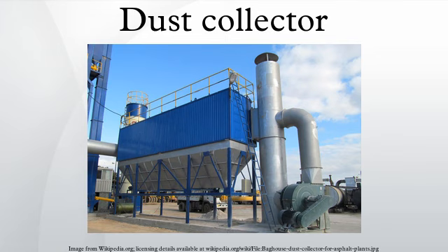These enclosures prevent free exchange of air between the inside and the outside, but they are not airtight. Totally enclosed, fan-cooled motors are another kind of totally enclosed motor. These motors are the most commonly used motors in dust collection systems. They have an integral cooling fan outside the enclosure, but within the protective shield, that directs air over the enclosure. Both open and totally enclosed motors are available in explosion-proof and dust ignition-proof models to protect against explosion and fire in hazardous environments. Motors are selected to provide sufficient power to operate fans over the full range of process conditions.